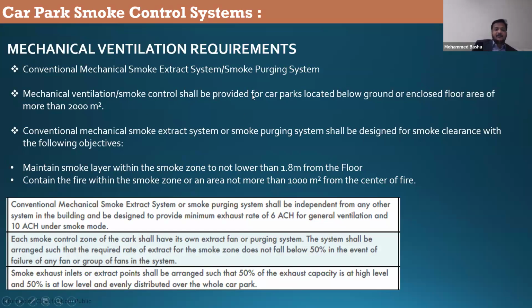So mechanical ventilation shall be provided for car parks located below ground or with an enclosed floor area of more than 2000 square meter. I told you the reason. This is the reason why they're asking. So the system, this smoke extract system or smoke purging system, shall be designed for smoke clearance with the following objectives. This is for the conventional ducted system. That's why the word smoke purging is here.